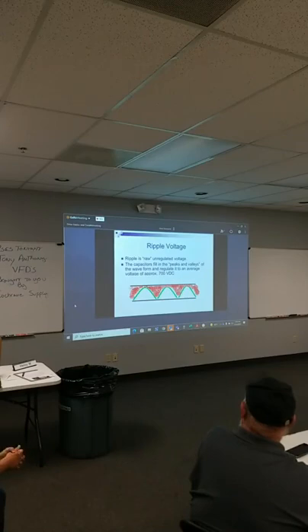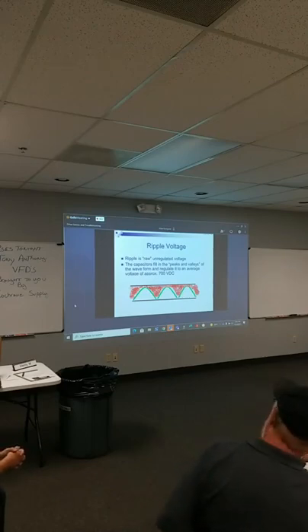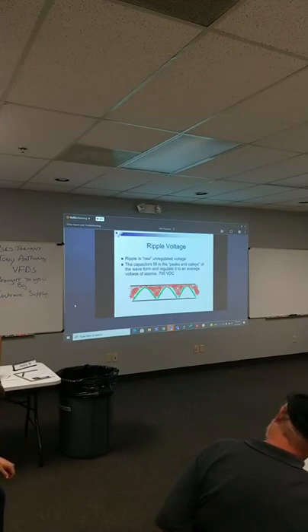So if you put a scope on a drive and you're seeing a lot of the green there with the ripples, you've probably got a capacitor that's on its way out because it's not able to maintain that DC bus. Or another thing you could have going on is single phasing. Let's say you have a three phase drive, but you lost a phase and you didn't know it. The single phase input creates a lot of ripple on that DC bus. So if you put a scope on the DC bus and you don't see a fairly smooth one, you've either got a capacitor that's going bad or you need to check your input and make sure you got all three phases solid.